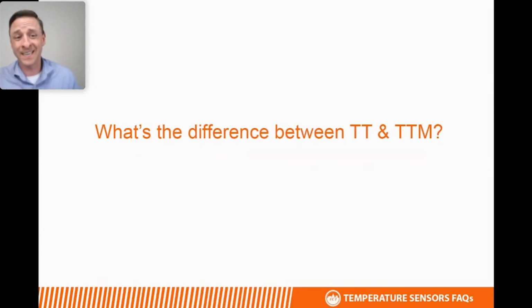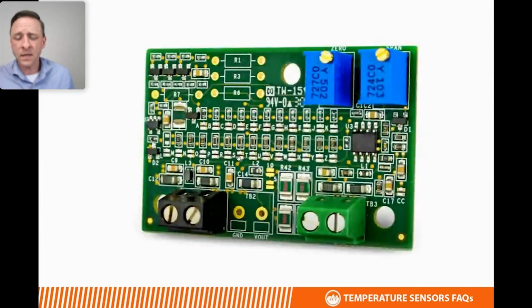So moving on to our TTs, that's our temperature transmitters. Our data sheet shows 2 different types, a TT and a TTM. And so the question is, what's the difference? TTM stands for matched. That means the sensor and the transmitter are built, tested, and calibrated together as one unit. That allows the calibration to calibrate out any of the sensor error. And the TTMs are also provided with an NIST calibration certificate by default as well.